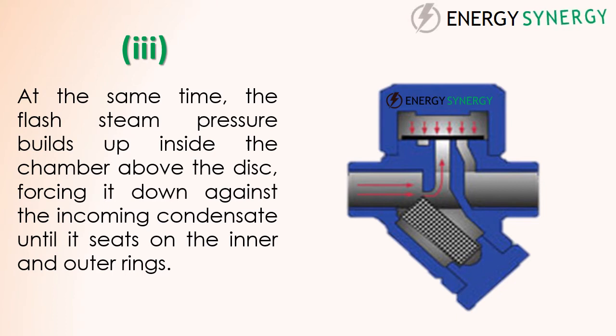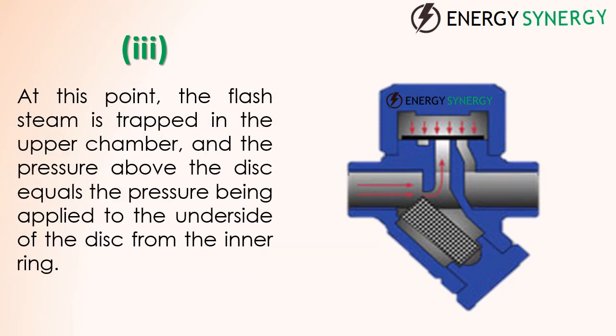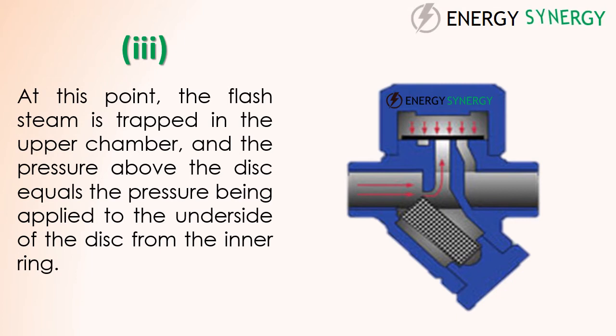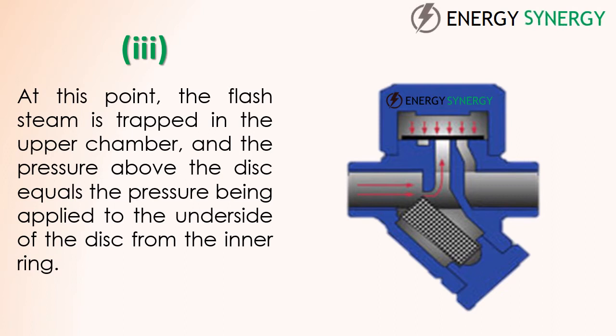The disc is forced down against the incoming condensate until it seats on the inner and outer rings. At this point the flash steam is trapped in the upper chamber, and the pressure above the disc equals the pressure being applied to the underside from the inner ring. However, the top of the disc is subject to a greater force than the underside, as it has a greater surface area.